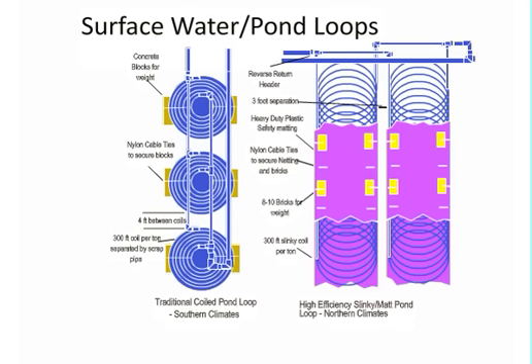I've seen issues there. You're seeing the slinky mat on the right-hand side, and again bricks and blocks kind of stacked on top of it. I prefer a PVC grid or something of that nature that separates that - you attach your blocks underneath and attach that to the PVC framework. The bricks can act as a bit of a leg to keep it up off the bottom, and it keeps it from abrading through the pipe and causing breaching of the pipe.